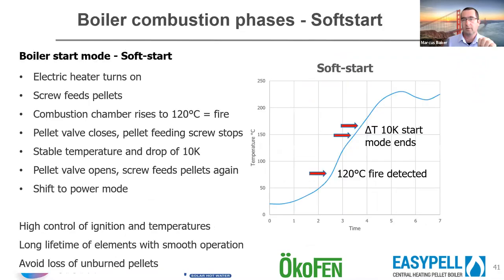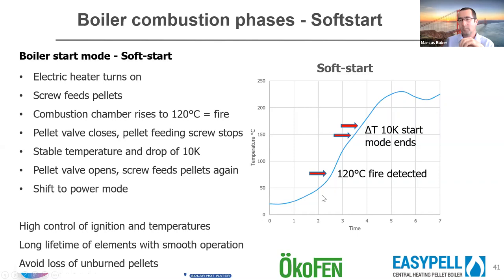Looking at how the boilers run: the Ökofen has a soft start where ignition is detected at 120 degrees, then it stabilizes and pauses essentially, flattening the curve before shifting into power mode. The Austrians are patient and calm — they let it move through the stages slowly, protecting components and achieving good longevity and controlled combustion. You really don't want to do what we do with gas — just turn on the burners at full noise.